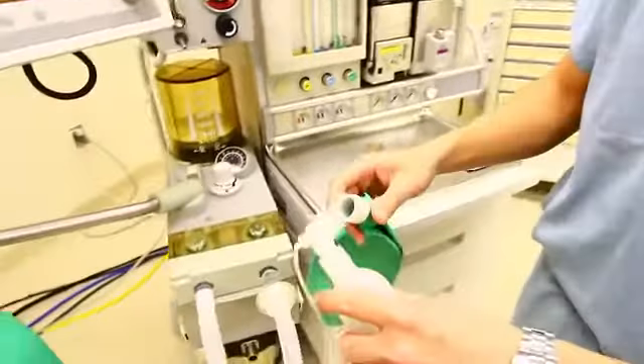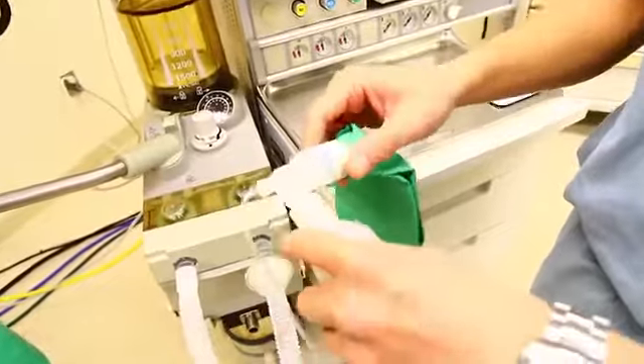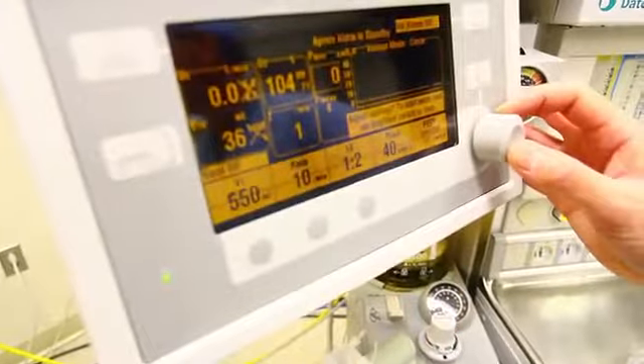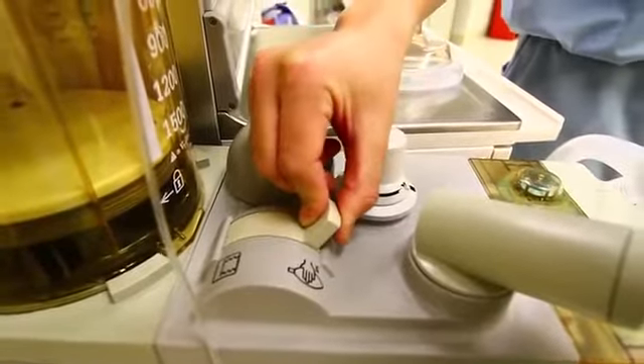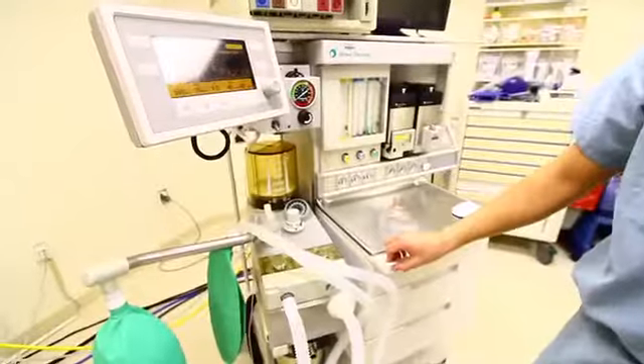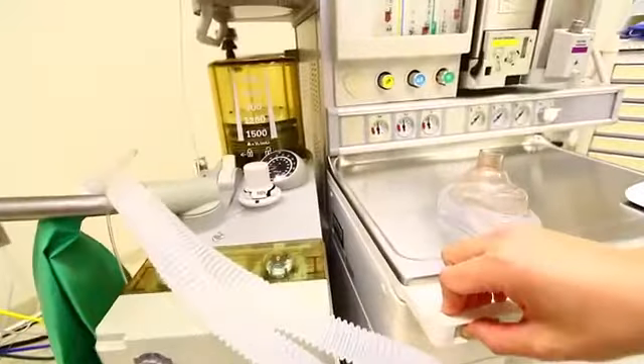Now we want to check the ventilation system and unidirectional valves. Place a second breathing bag on the Y piece. Then set appropriate ventilator parameters. And then switch it to automatic ventilation. Fill the bellows and breathing bag with the oxygen flush valve.